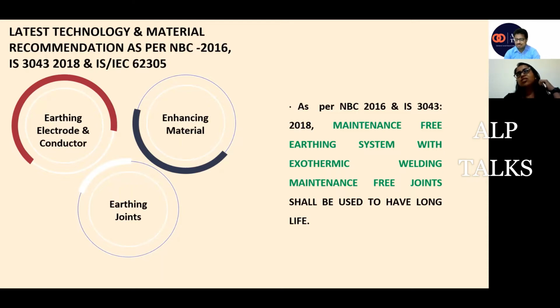Also, I want to clear one point here. There was a misconception that for transformers and DG sets, we should use only copper plate earthing, and that maintenance-free earthing should be used only for lower, low size equipments. But it is not so. We can install maintenance-free earthing with solid rods and chemical compound for every application. It will work better, and it will provide you better results for your equipment and for human safety too.